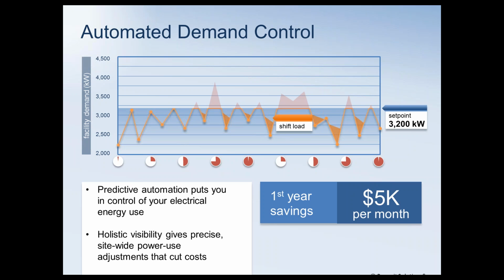And in Mike's slides, he went through some of the facility melting operations where there was dead time in the melt operation and you're trying to smooth in. That's exactly the time frames that we took advantage of at Canon Muskegon by doing demand management and demand control. We were able to shift our melting time period at a reduced peak power, lasted a little bit longer, but we took significant cash advantages of being able to smooth that trend line to a set point. Next slide, please.